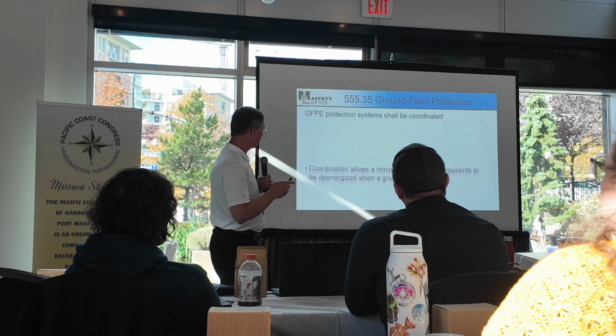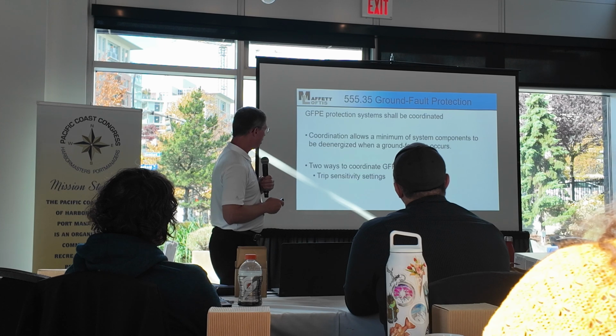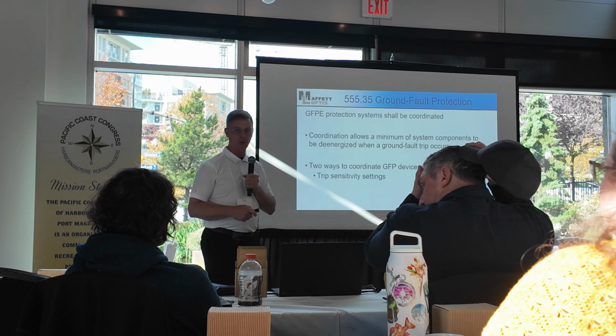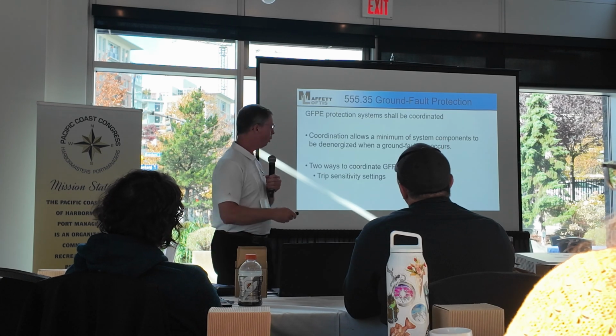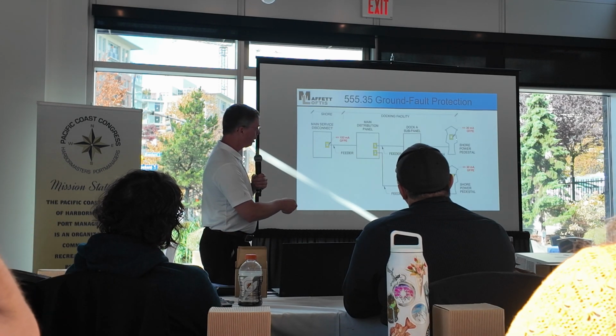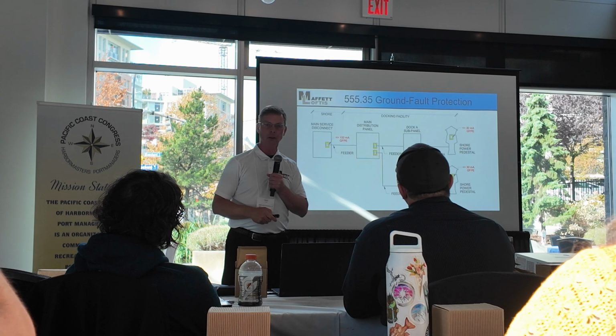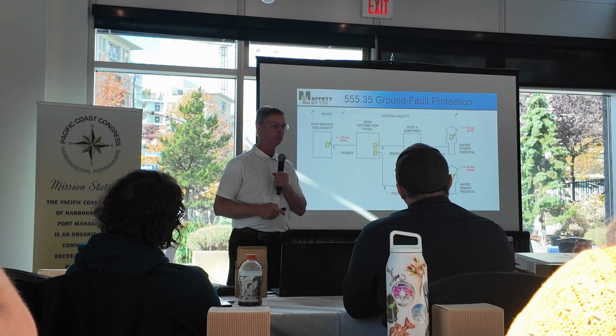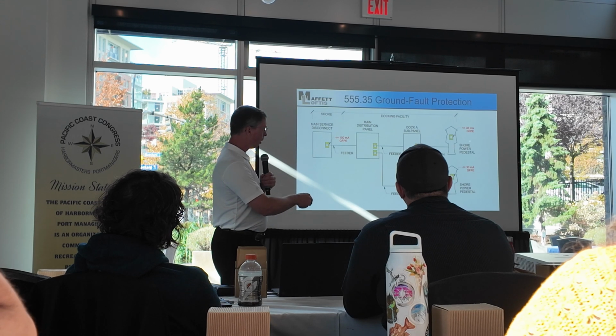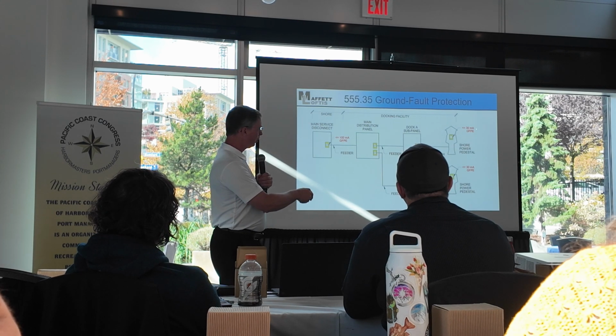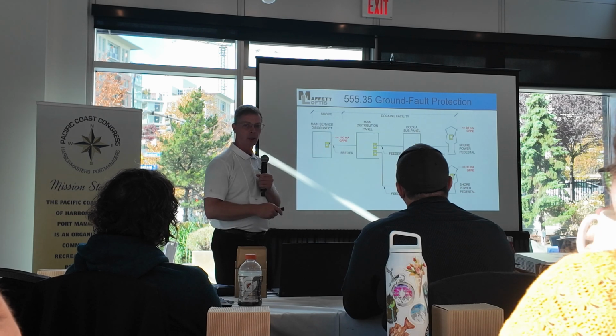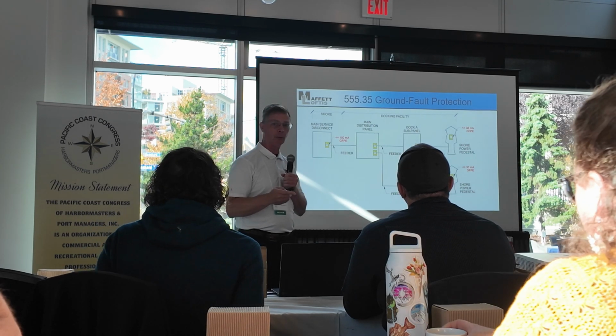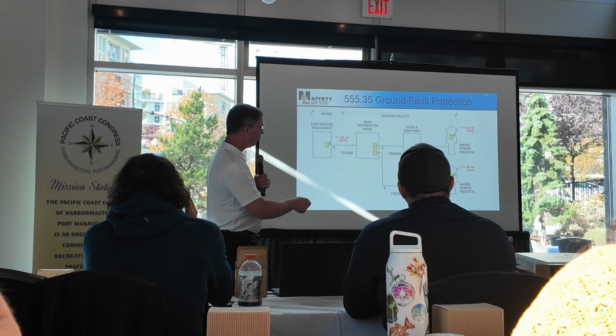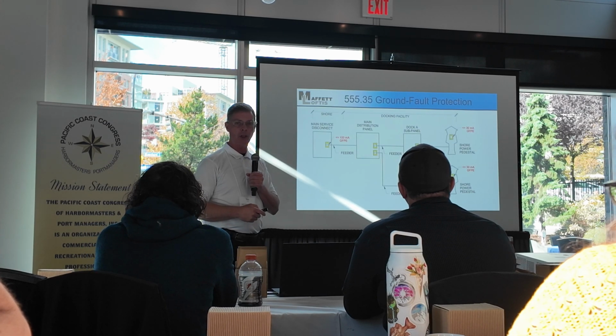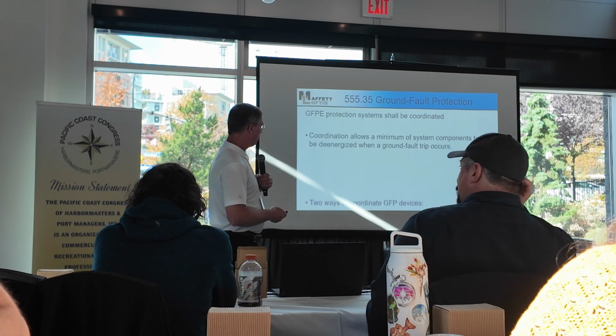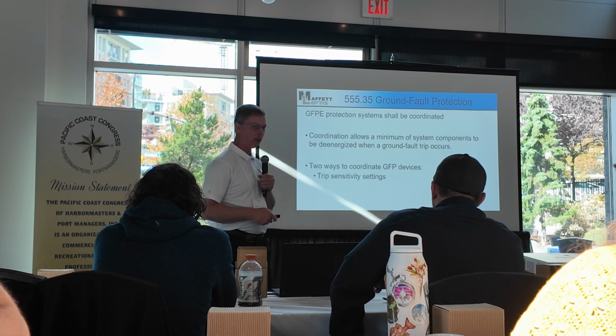And what I mean by that is this. There's two ways to coordinate. You can coordinate with the sensitivity trip level, right? Which is that 30 milliamp or 100 milliamp. Go back here. What if this boat right here, say that boat instead of 400 milliamps, it pulls 40 milliamps of leakage current. What would trip? It would trip right there, correct? Yeah. Because that 40 milliamps is greater than the 30, but a lot less than here, so it would trip locally. That's what you want. But if it's greater than the 100, then you're in trouble. So here is a means of coordination because you've got the different trip levels. So that is one means of making coordination.